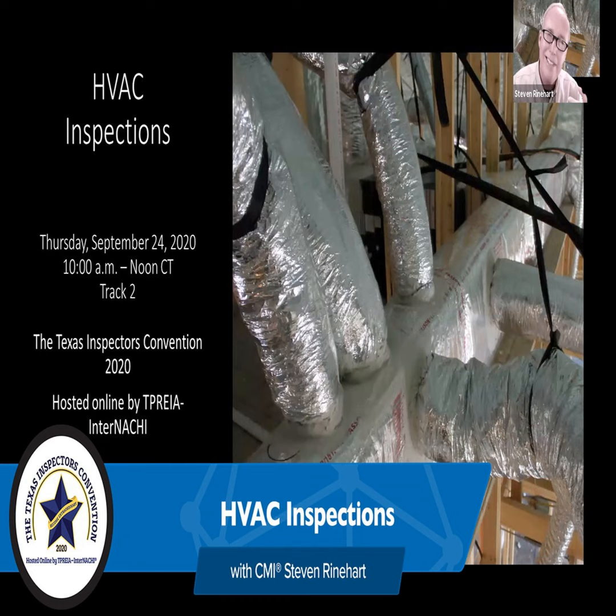Requirements for gas. Gas leaks, not required to have sniffers. We've got a few, but they put that additive in gas so you can smell it. And that's kind of what they're looking for. In a closet, if it's leaking, when you first open the door, you kind of stick your head in. Do I smell anything funny in here? That's gas. Flame impingement, we talked about that. Uplifting, flame color, scale buildup. Definitely want to look at that before you start it up. I look at that on water heaters and on furnaces.